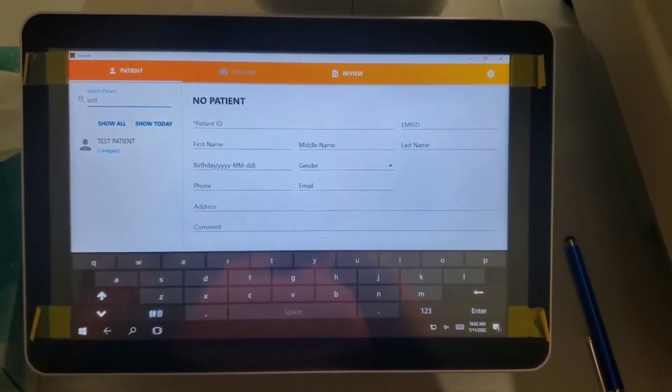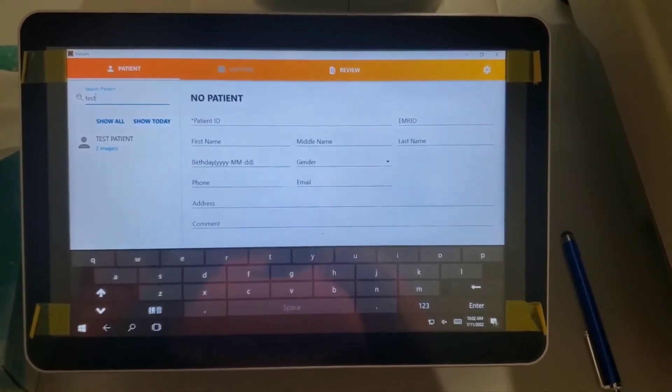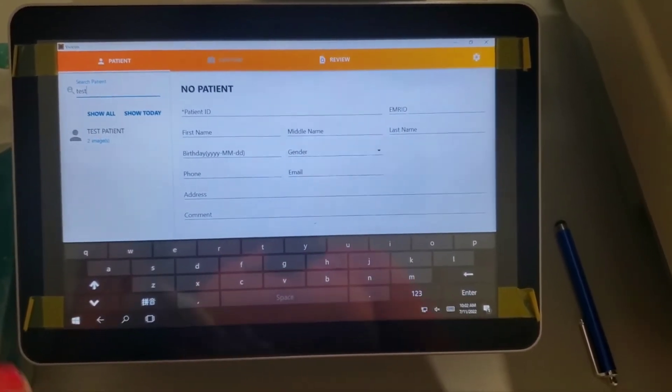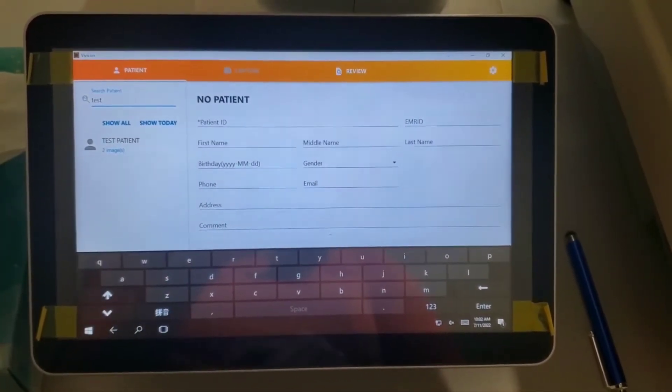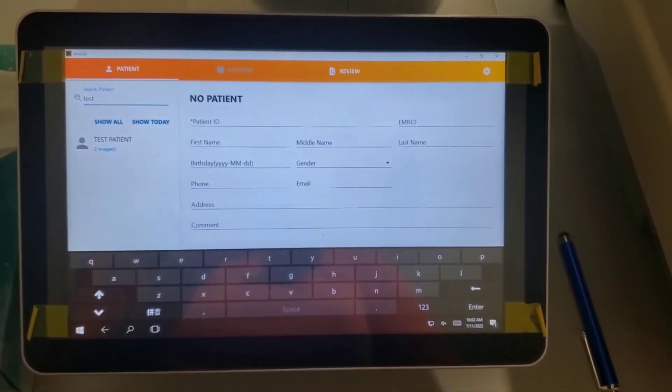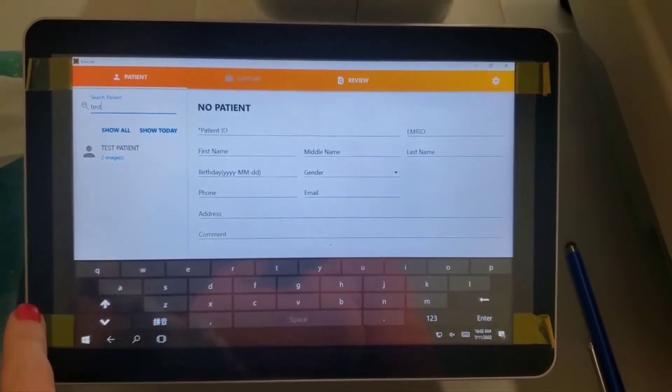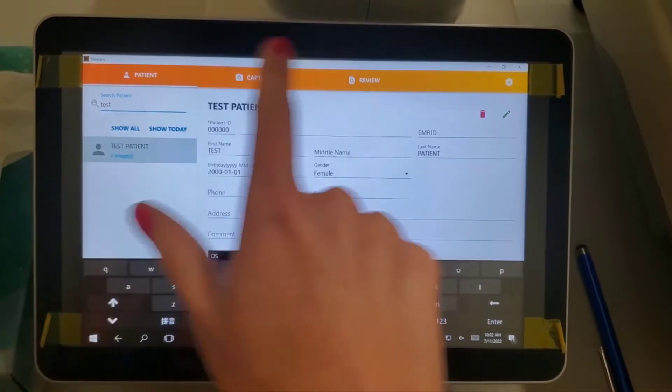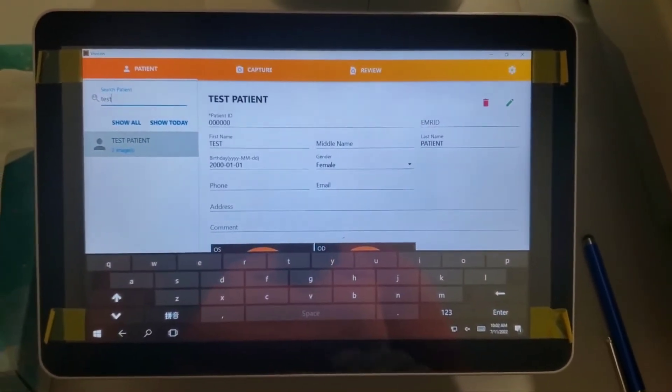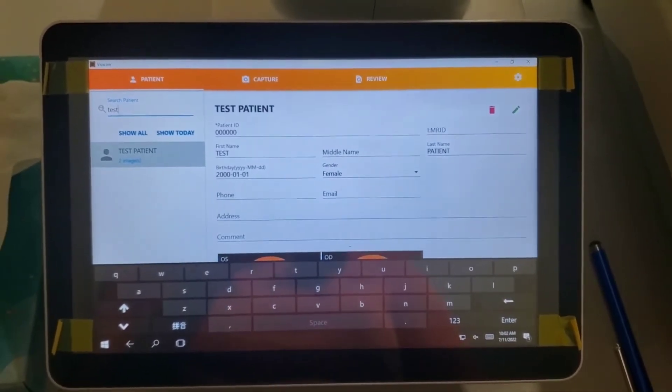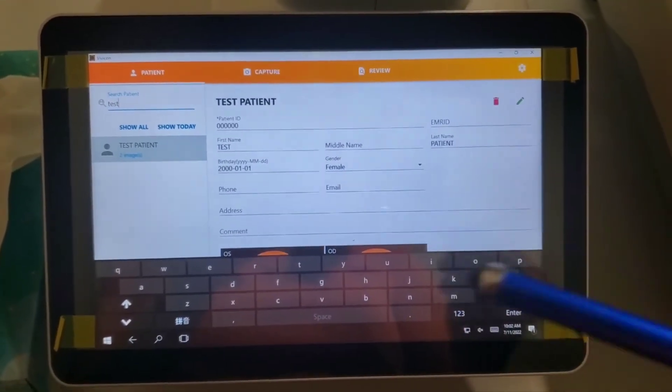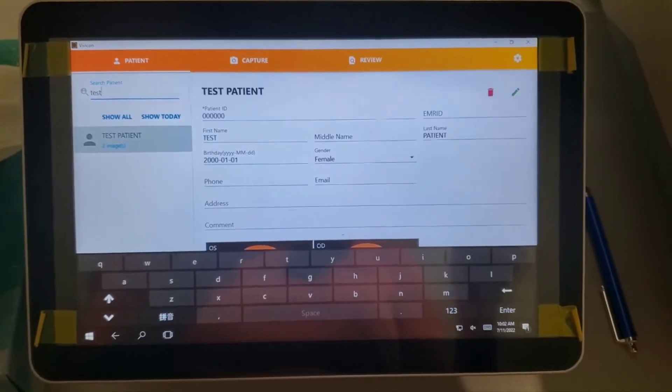If they are an established patient who has done this machine before, they should be in the database. Here under search patient, you're going to type in their last name. I'm going to use a test patient for today. If they are in the database, their name will pop up here and then you click it. This screen is touch screen. Sometimes it's really touchy. You have to sometimes hit the buttons multiple times. There is a stylus that we keep next to the machine if you'd rather use that. Once you have your patient's name pulled up, then you would hit capture.